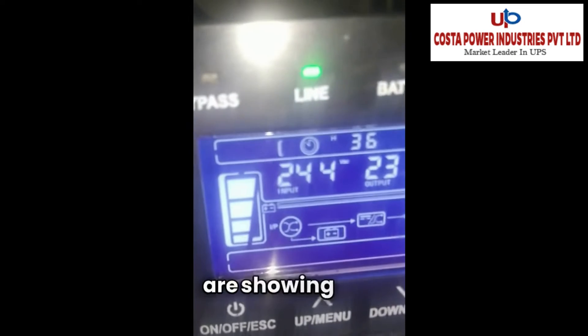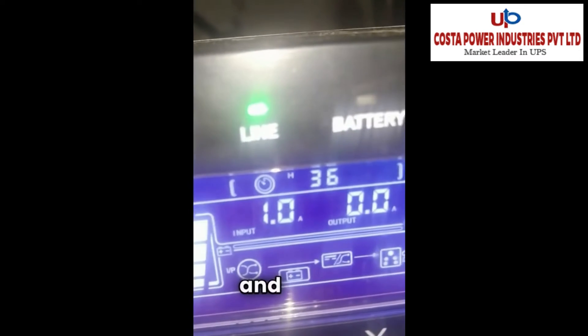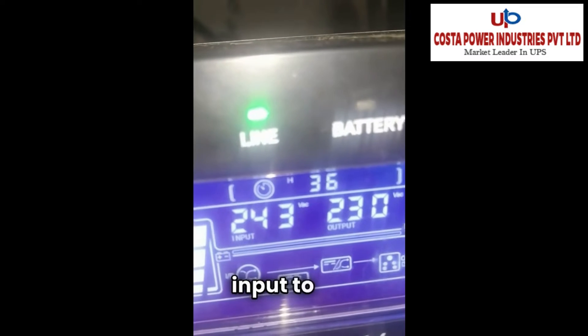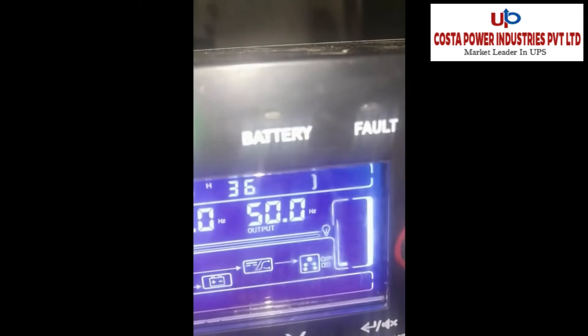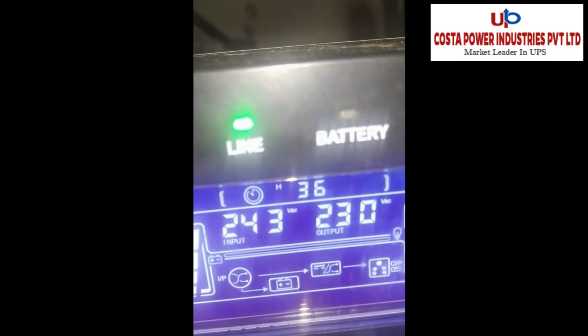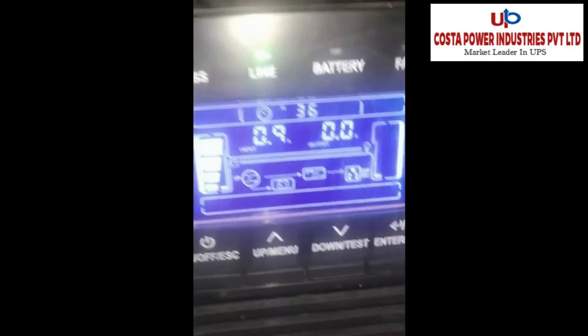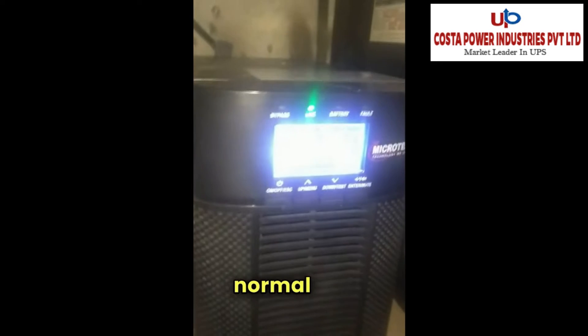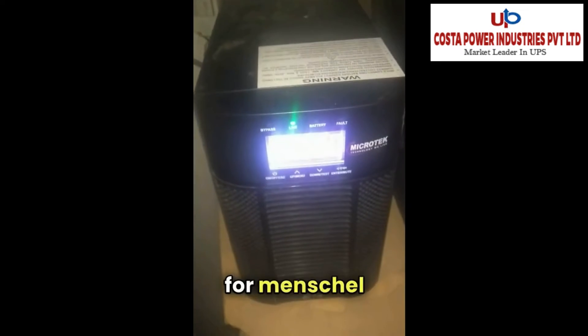All parameters are showing here. The first block shows battery charging, and this is the input at 243 volts. Output current is 0, and output voltage is 230 volts. This is the normal line operation of the UPS. I will now check for the mains fail test.